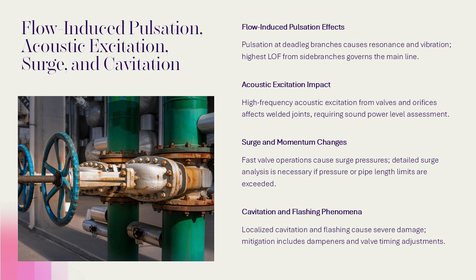Cavitation and flashing are localized but severe phenomena at discrete pressure drops. Flashing typically results in LOF of 1.0, while cavitation yields LOF of 0.7. These mechanisms demand targeted mitigation, such as installing pulsation dampeners, low-noise trims, or adjusting valve timing to reduce dynamic loads.